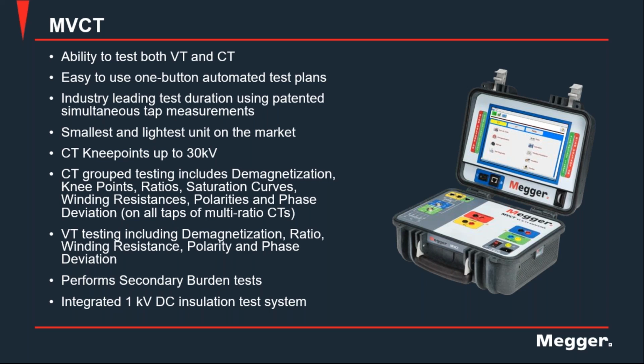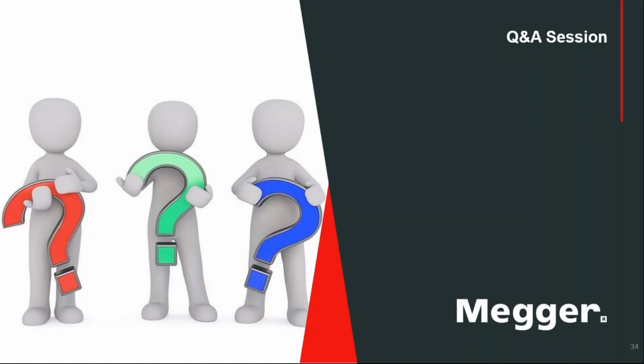It's a lighter instrument because now you don't have a transformer that goes up to 2 kilovolts, and it provides the same features as the MVCT, with the only exception that you cannot test CVTs with this one. You have to use higher voltage for CVTs, and so this instrument won't apply, but you can still test the insulation resistance. You can also test burden and do all the other tests, and it will perform the same assessment on all of the instrument transformers that it can test.